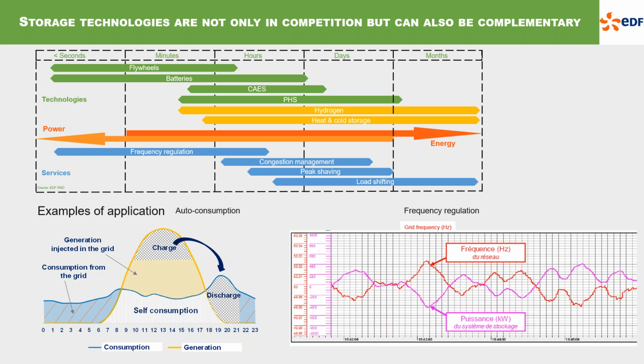On the right is frequency regulation, shown here as primary reserve, where assets are contracted by the grid to react very quickly, within about 30 seconds, to counterbalance power imbalances and prevent the frequency from deviating from 50 Hertz. This application is much faster in response time—here you see only a few minutes—and requires far fewer cycles and much less energy to provide the service.